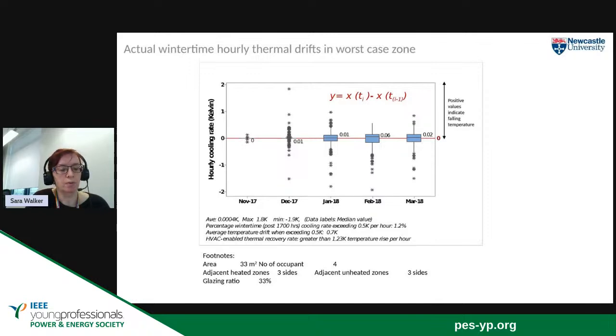We also found that once we switched the heating back on, the building recovered quite quickly. It recovered back to the 21 degree set point in about half the time of the demand response event. So if we offer demand response for 2 hours, we could recover the temperature back to its set point after an hour of the heating going back on.